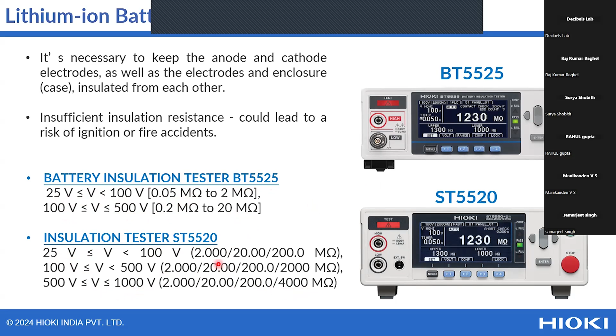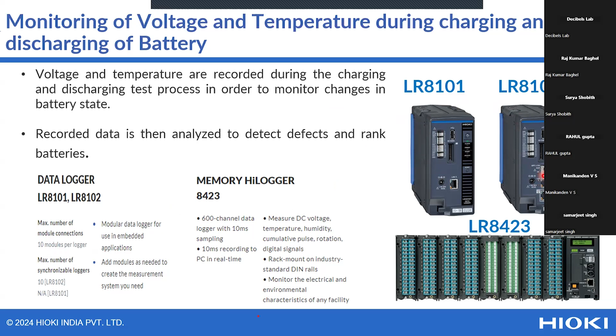Now, next one is the voltage and temperature recording instrument, that is LR8101 and LR8102. These are also recent ones launched by Hioki. And before that, there is one model, LR8423. So these are the recent ones, and before that, it is this. With this, you can connect 10 modules with this data logger, and you can connect 10 data loggers at a time. So by this combination, you can tap voltage and temperature of up to 3000 channels at a time, because in each module you can measure 30 temperatures. So 10 modules you can connect, so 300 channels, and 10 data loggers you can connect by using optical. So 3000 channels you can tap at one time. So these are the specifications of these data loggers. The basic difference between these two is that in this there are two LAN ports and an optical connection is also available for synchronizing.